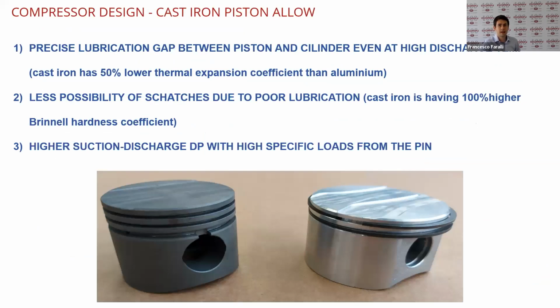Then we have cast iron pistons, and this is also a unique feature of our compressor compared to all our competitors that are using aluminum. So the idea is that since the crankcase is made of cast iron, we have the same material for the piston, because for CO2 the discharge temperature, as I said, is very high, and so we have the same thermal expansion between the piston and the crankcase, and in this way we have the lubrication gap between the piston and the cylinder that is always the same.